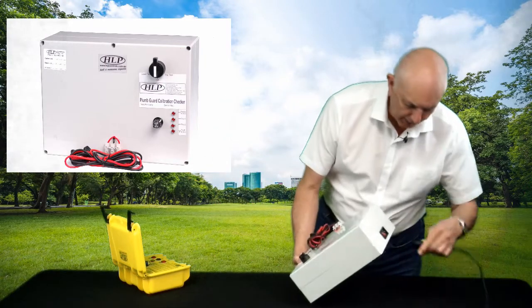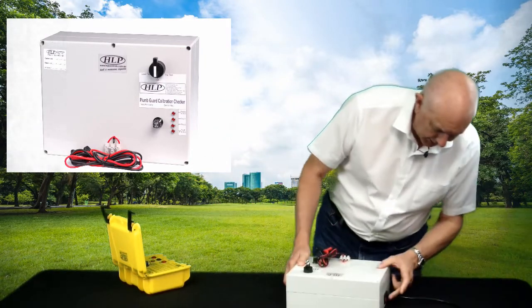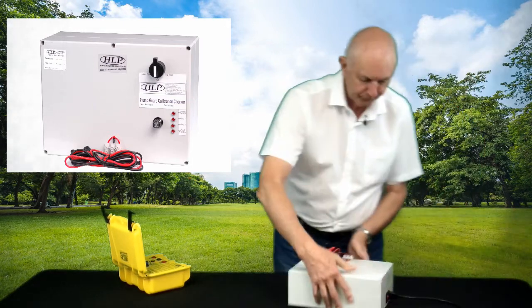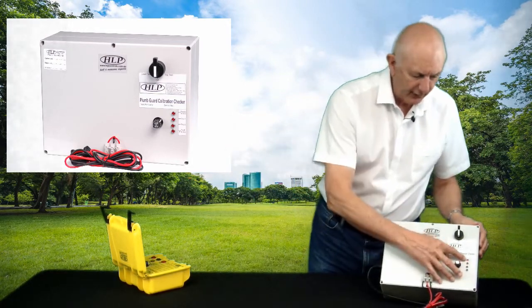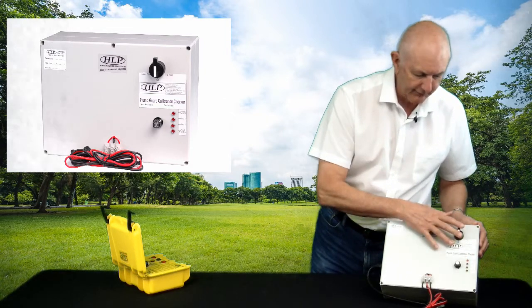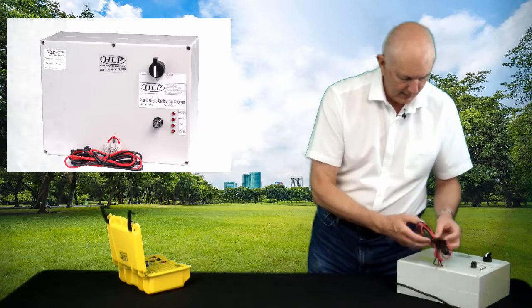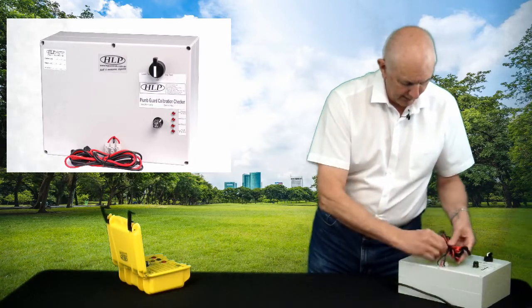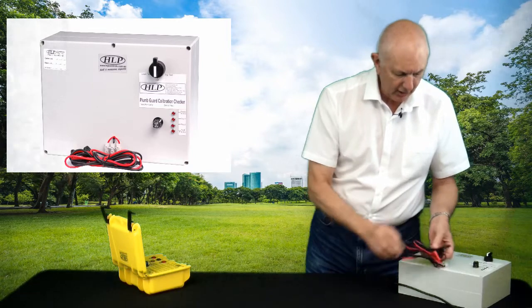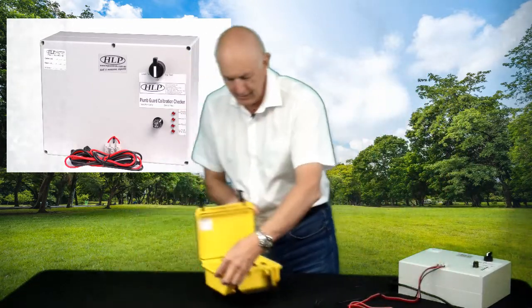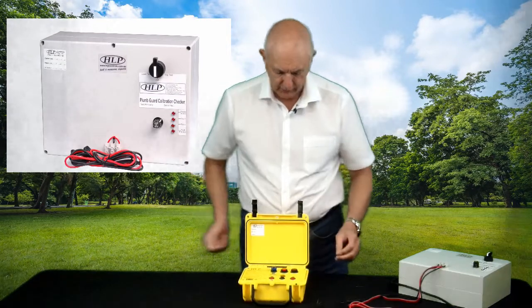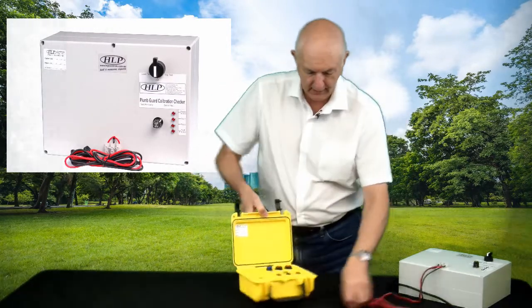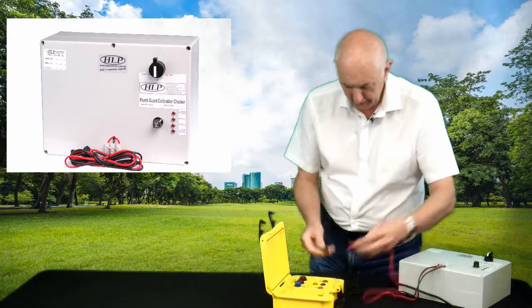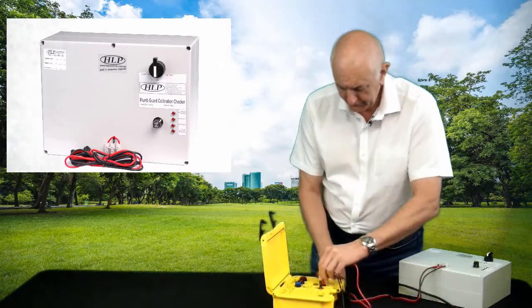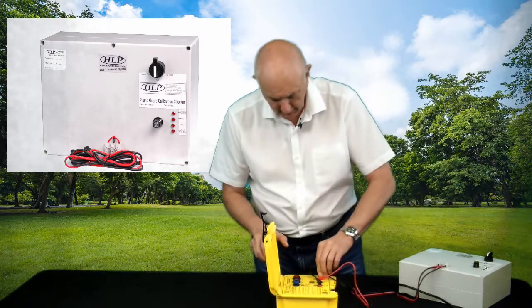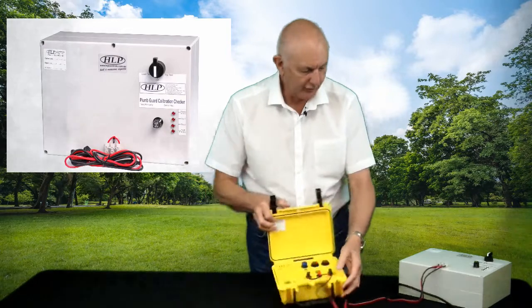So to use the kit, we plug in some mains, and it's an on-off switch, and we turn the switch on. When that happens, you'll see that one red light comes on, and we have a selector switch at the top. So disconnect the tie holding the 3 test leads together, and using a normal Pump Guard, push the on-off button to power the Pump Guard. While that's doing its own self-check, plug in the 3 leads supplied from the calibration and check kit.